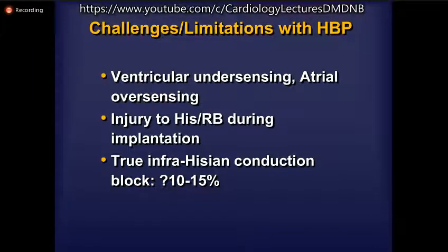Thirdly, remember I showed you the anatomical location of where your lead is sitting, like hanging at the AV junction, and therefore there is a risk of ventricular undersensing and atrial oversensing with the location of the His bundle lead. There is also a concern, though not borne out much by practical experience so far, that there could be an injury either to the His or to the right bundle during implantation.